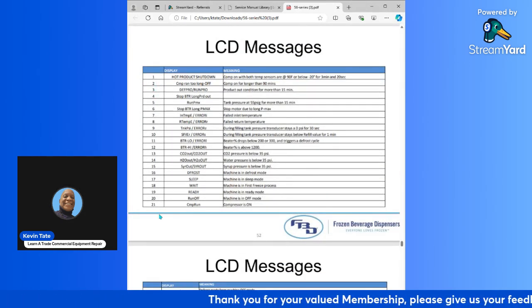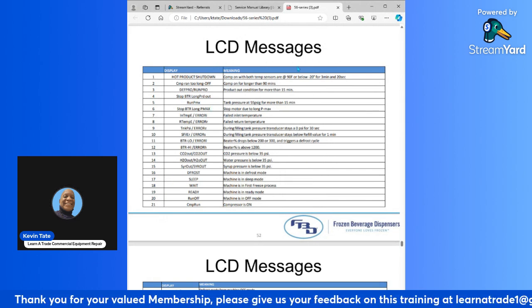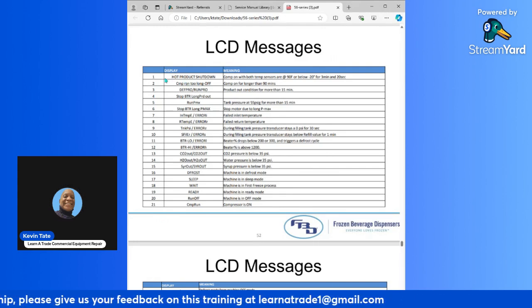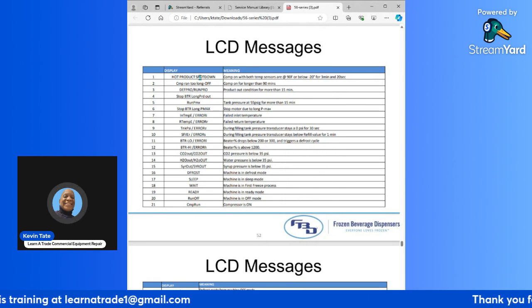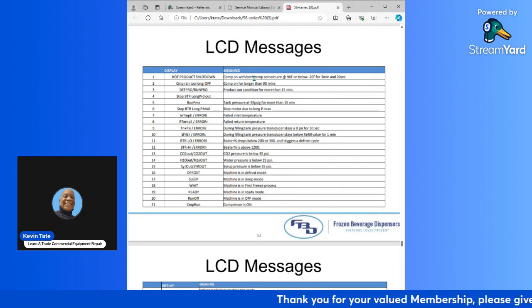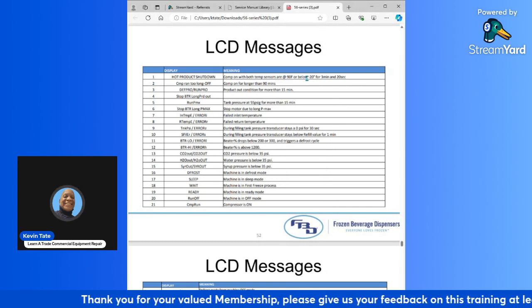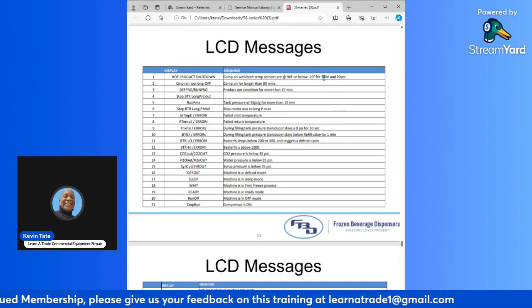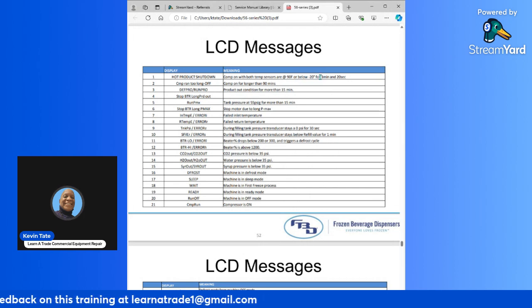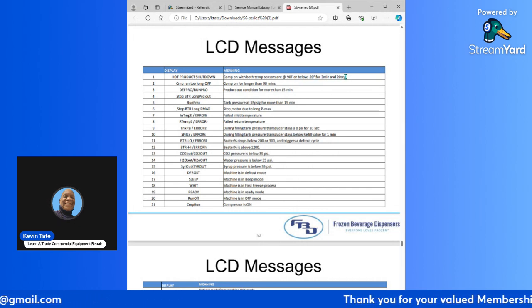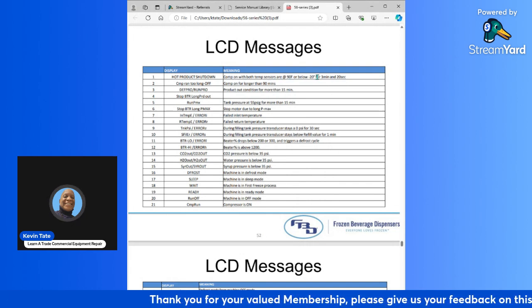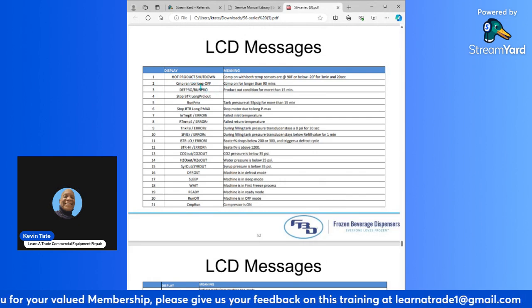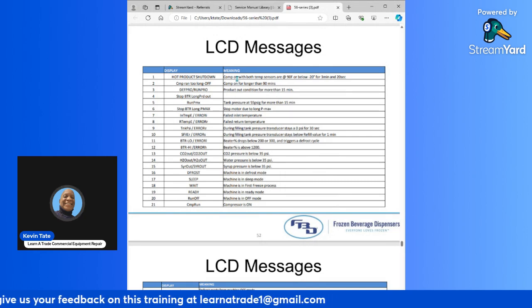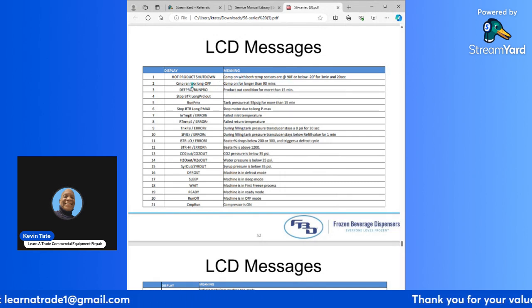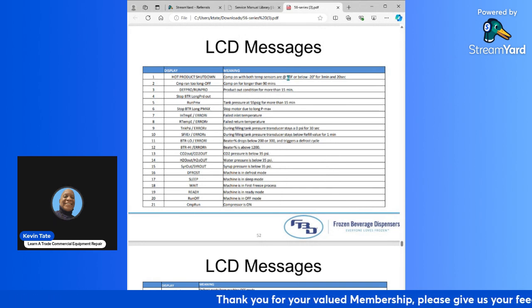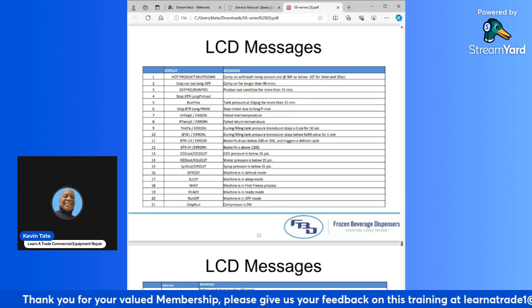And here is a list of some of the LCD messages that you will see on the FBD units. The first one you're going to see commonly is hot product shutdown. The meaning is the compressor was on with both temp sensors at 90 degrees or below -20 degrees. So the sensors could be reading wrong for 3 minutes and 20 seconds. If a sensor senses one of these temperature levels, it's going to go into a hot product shutdown. In that case, you would have to go into the readouts and test your sensors to see if any of them are at 97 degrees. When a sensor's at 97 degrees, it's bad and you'll need to change it out.